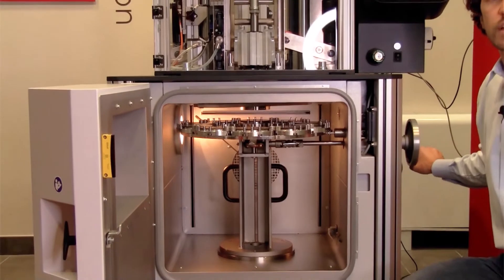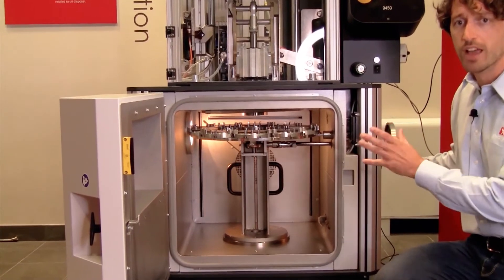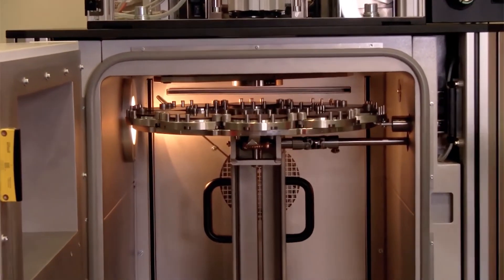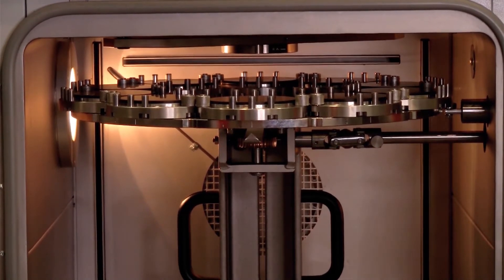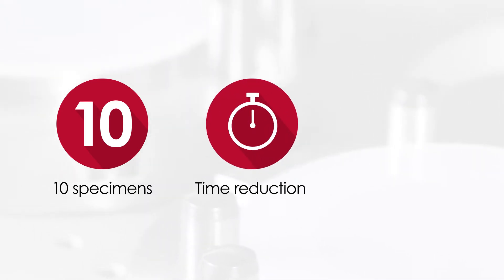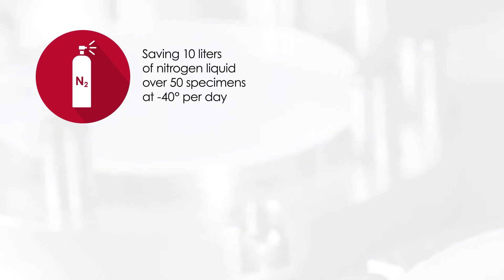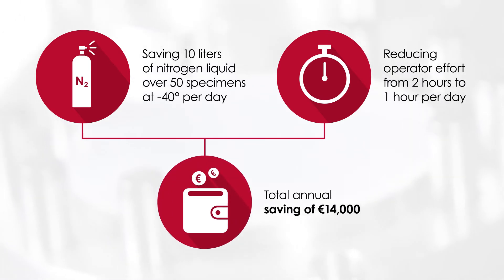Its versatility allows testing both thin films and rigid plastics. If you are concerned about any possible positioning error, the carousel system is equipped with sensors that finely control the disc positioning. Using the carousel system to condition and test 10 specimens inside the thermostatic chamber is crucial to speed up testing as well as reducing liquid nitrogen consumption — avoiding opening the chamber after each impact can save more than 10 liters of liquid nitrogen every 50 specimens and reduce by half the operator's time, mostly wasted waiting for thermal stability.